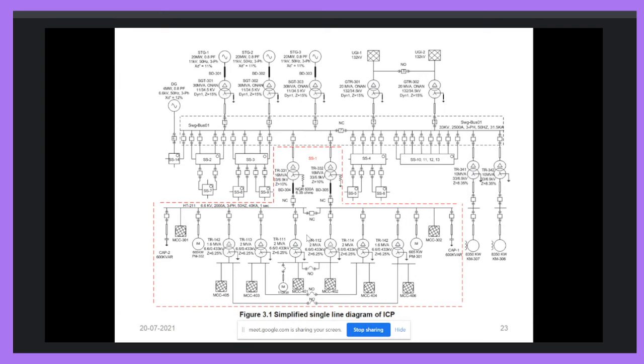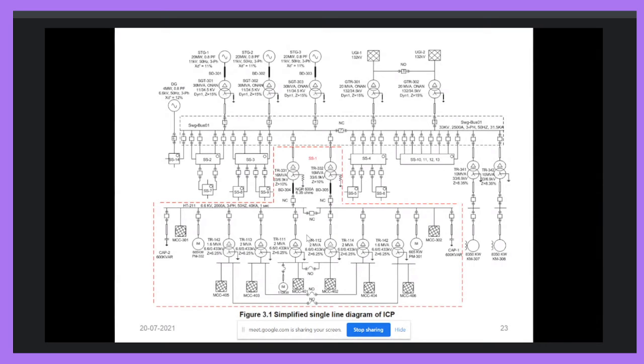process, for which they require steam. The same steam is utilized for the generation of power. They have their own generation of 60 megawatt, and they are drawing the mismatch of load and generation from the utility grid. Whatever requirement is not fulfilled by their own generation, they draw that power from the utility grid. Here you can see the different substations, like SS1, SS2; there are 14 substations. The configuration of the system inside each substation is presented inside the dotted line.